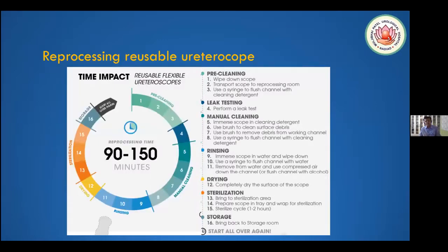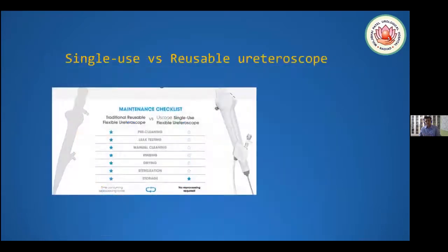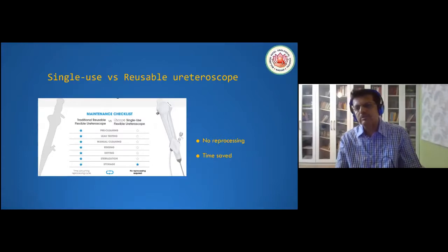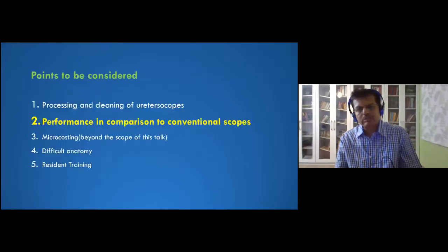But what is important, you see the amount of time that is required for doing all these things. The pre-cleaning will take approximately 10 minutes, then manual cleaning for 10 minutes, rinsing, then actually going to the sterilization, storage, and then start all over again. So this will add to the cost, and particularly when there is a high volume center, this would be very much detrimental, particularly in large turnover cases. So single-use ureteroscopes actually overcome all these problems. There is no reprocessing time. The time saved is actually the time saved for the patient, and it is actually money saved. That would be the first reason why I feel that flexible disposable ureteroscopes would be there.